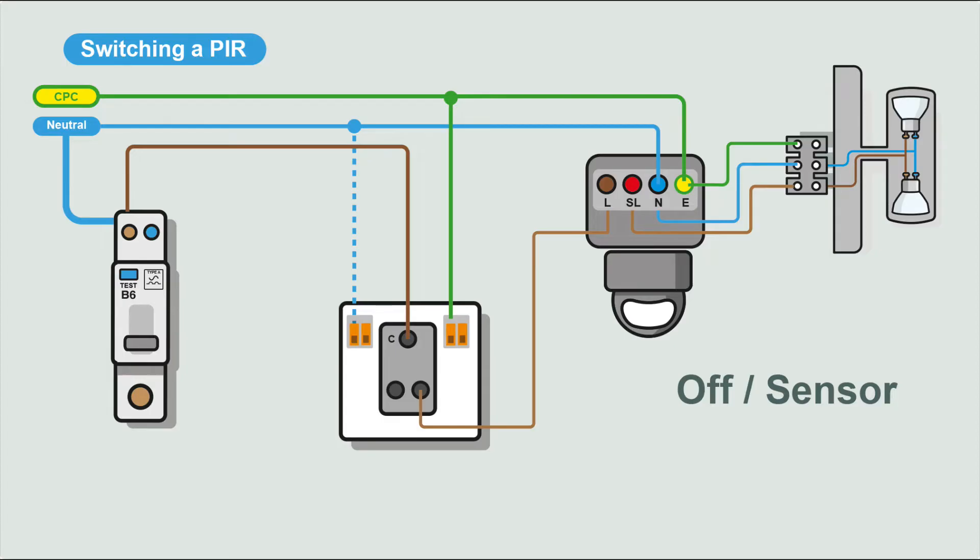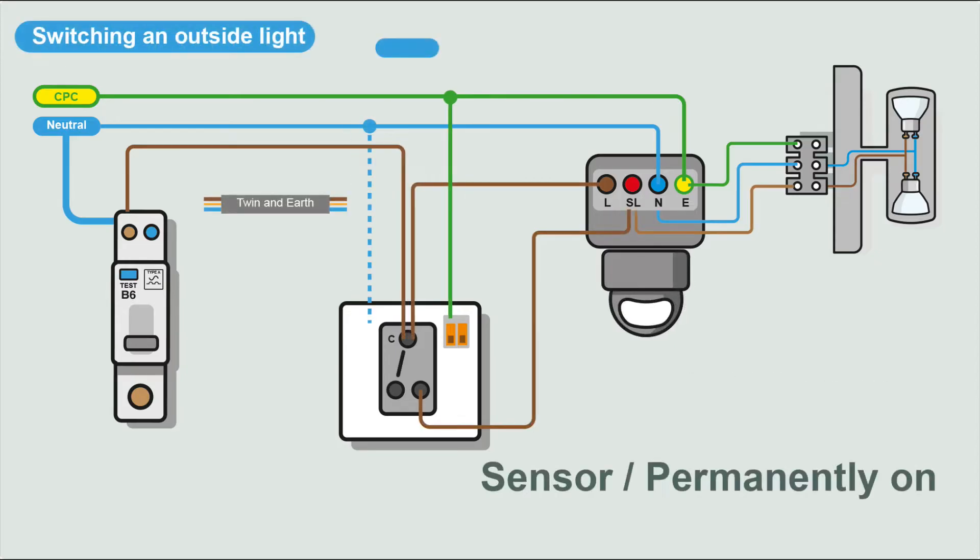Sometimes it's nice to have that functionality of being able to switch the light on permanently. In this example, a feed comes in on the common and leaves the common to the permanent live in the PIR. From L1, we take a feed to switch live in the PIR, which then energizes the light. So in the off position, the light is operated just by the sensor. In the on position, the light is permanently on. The issue with this setup though is you can't actually switch the whole thing off. It's either on sensor or it's permanently on.